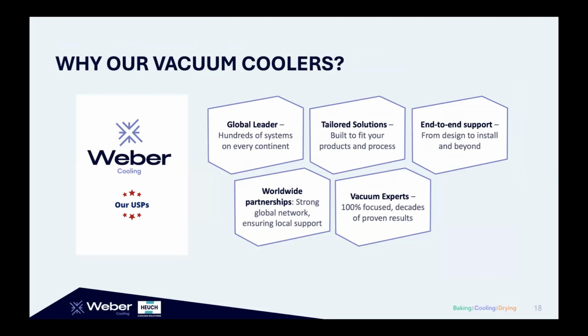Why Weber? Well, as I explained, we are worldwide present, and we focus on vacuum technology. So we have a very wide knowledge of the best configuration of systems to really obtain fast cooling times. We know exactly what vacuum capacity you need, what are the best pumps, and the best cooling capacity. The cold trap size is important to absorb all the moisture, because you don't want any moisture in your pumps.